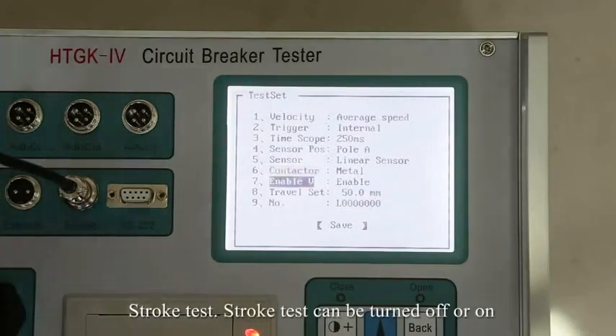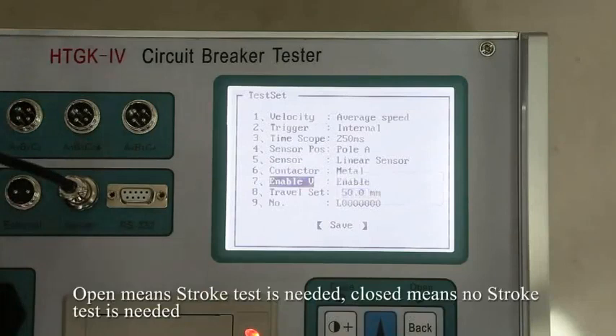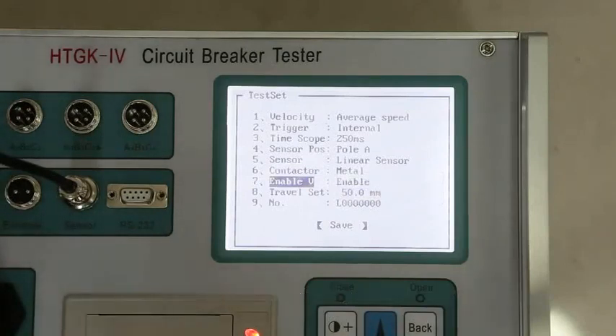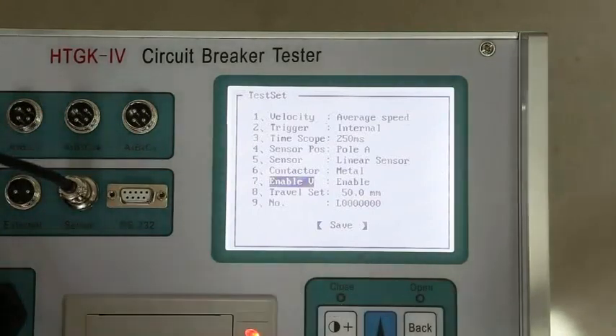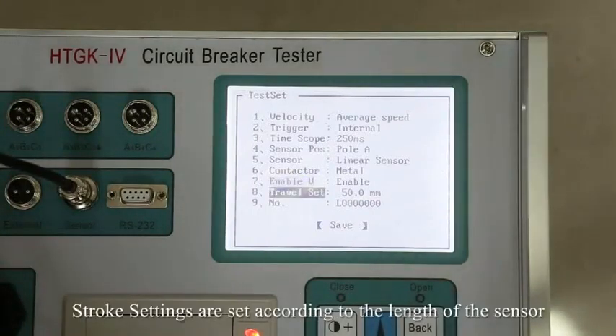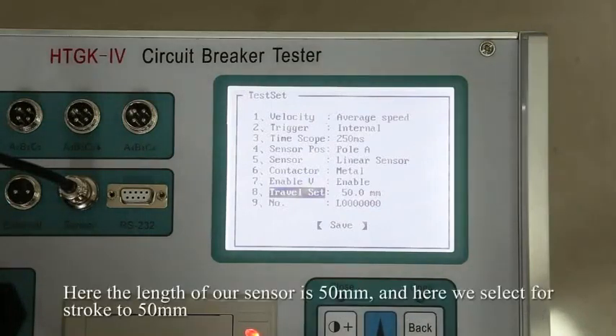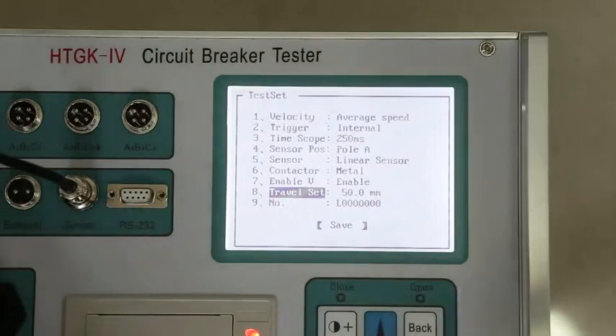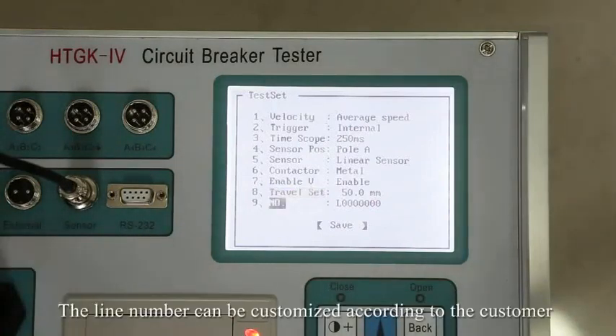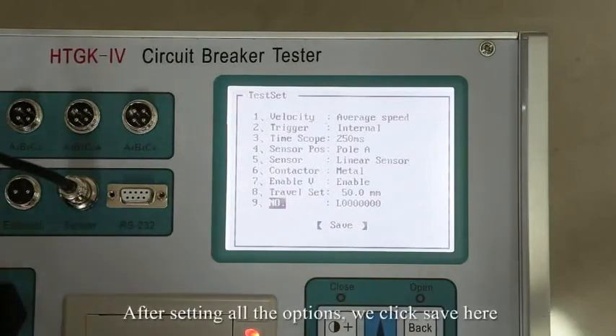Stroke test can be turned off or on. Open means a stroke test is needed. Closed means no stroke test is needed. Here we select open. Stroke settings are set according to the length of the sensor. Here the length of our sensor is 50 mm, so we set the stroke to 50 mm. The line number can be customized according to the customer. After setting all the options, we click Save here.